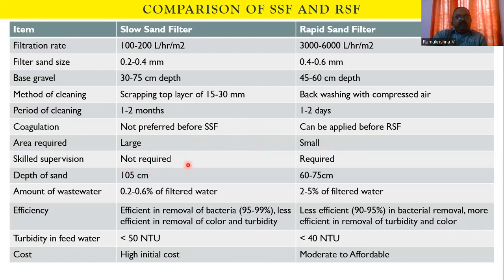Skilled supervision is not required, just allowing the water. Only cleaning is very simple operation. Whereas the rapid sand filter, the number of valves to be opened and closed during cleaning and backwashing operations, so it requires a skilled operation. Depth of the sand, 105 centimeters, 60 to 75 centimeters.